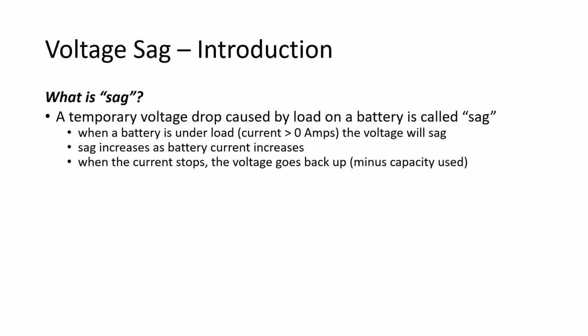What is it? It is a temporary voltage drop caused by load on a battery. When a battery is under load, meaning that there is current flowing, the voltage will inevitably sag. This sag increases as the battery current increases. Doesn't matter what the motor current is, it matters only what the battery currents are. So, as I said, it's temporary. So when the current stops, the voltage will go back up, obviously minus whatever capacity has been used.